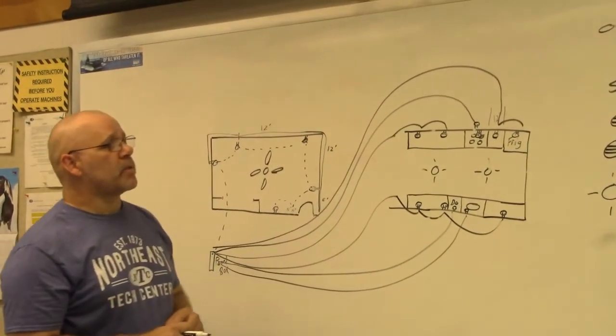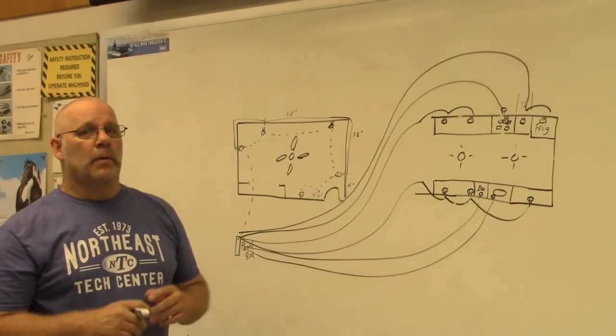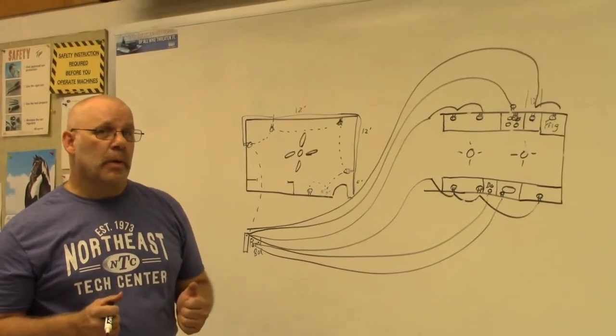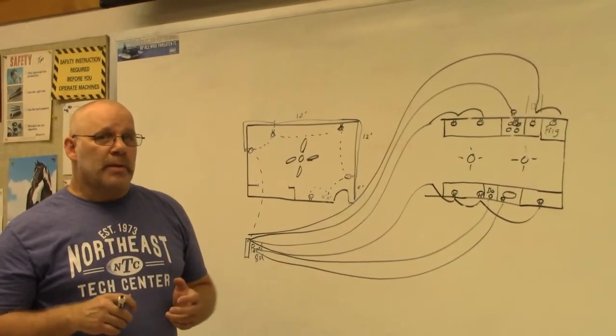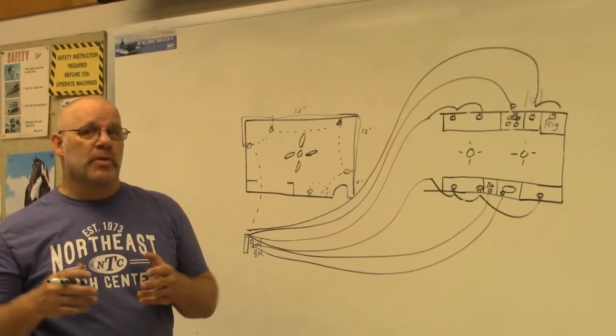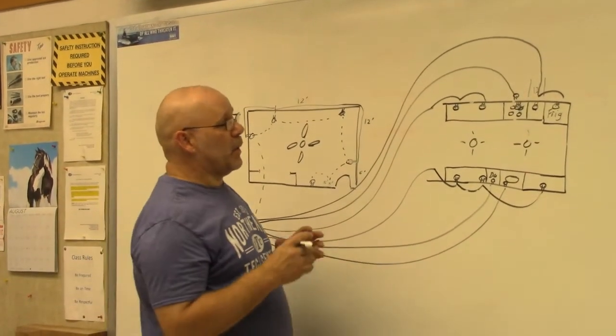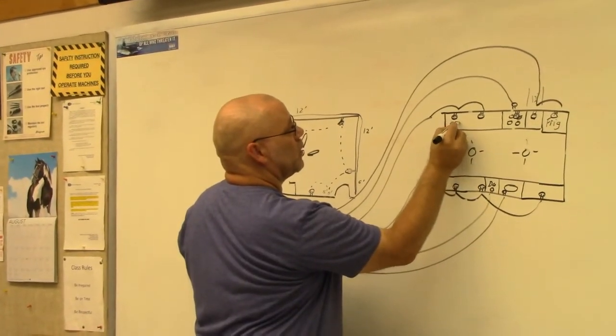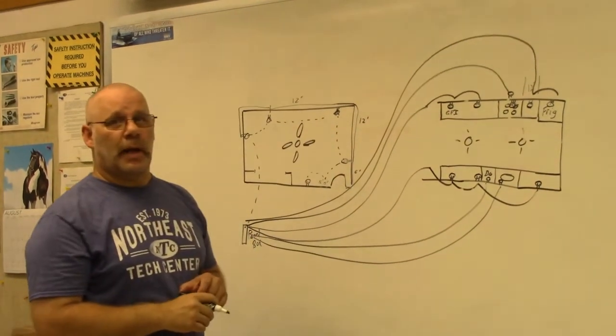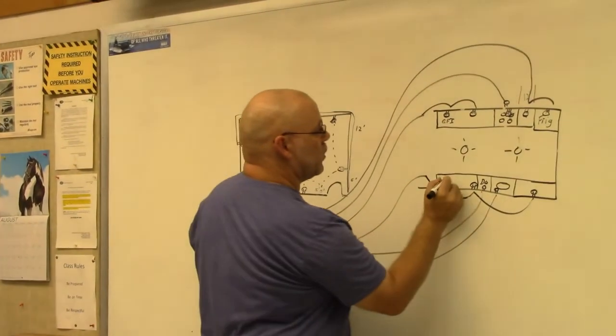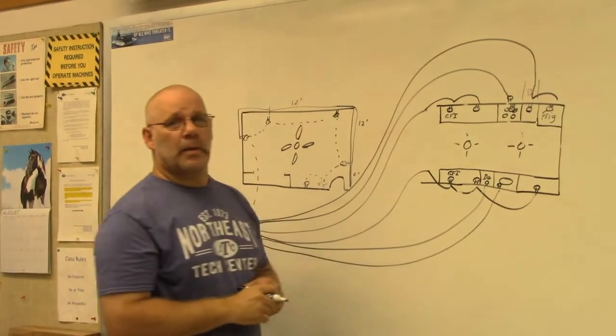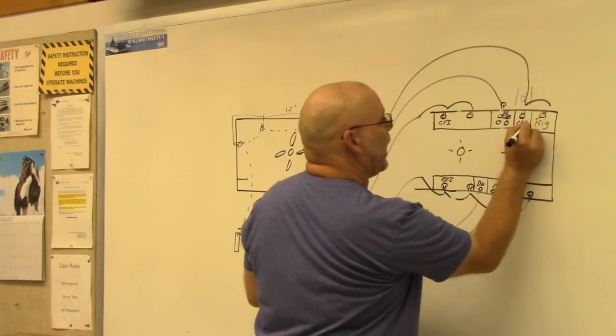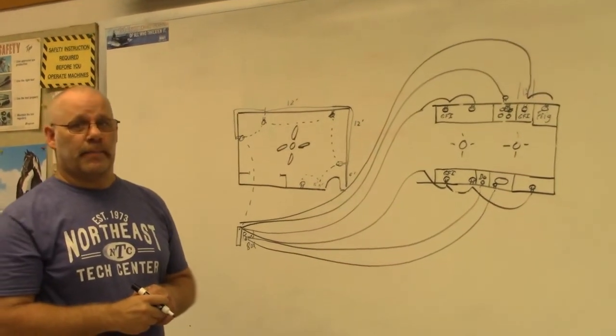Now, GFIs. Kitchen has to have GFIs because there's water in the kitchen. Where would the GFIs go? GFIs have to be on the first item of the circuit. So in my case, in my example here, this one would have to be a GFI. This one would have to be a GFI. This one would also have to be a GFI.